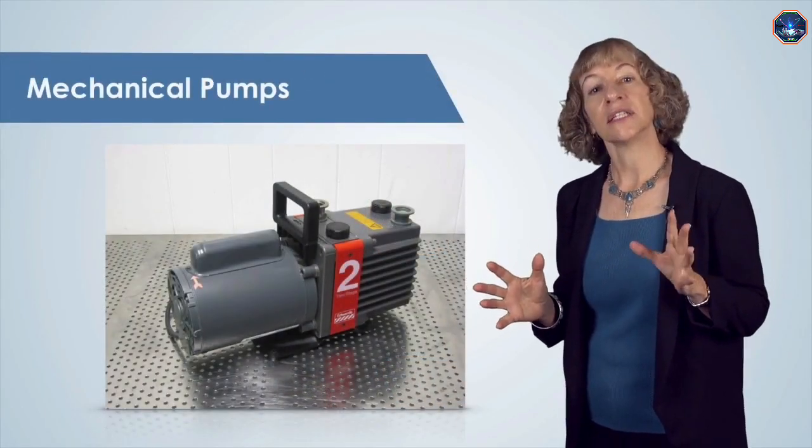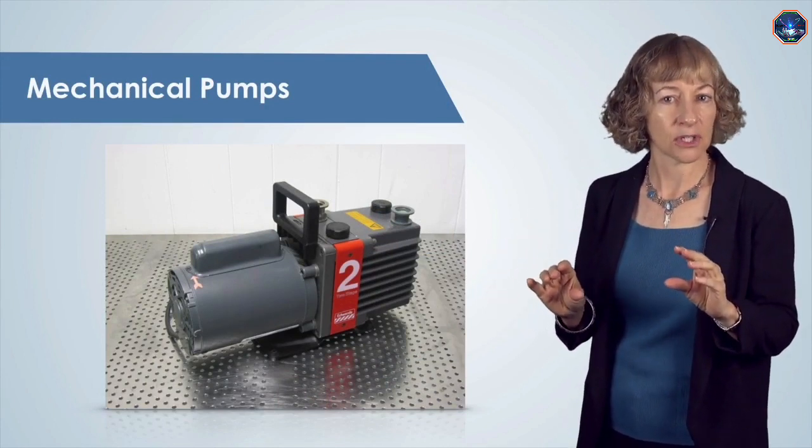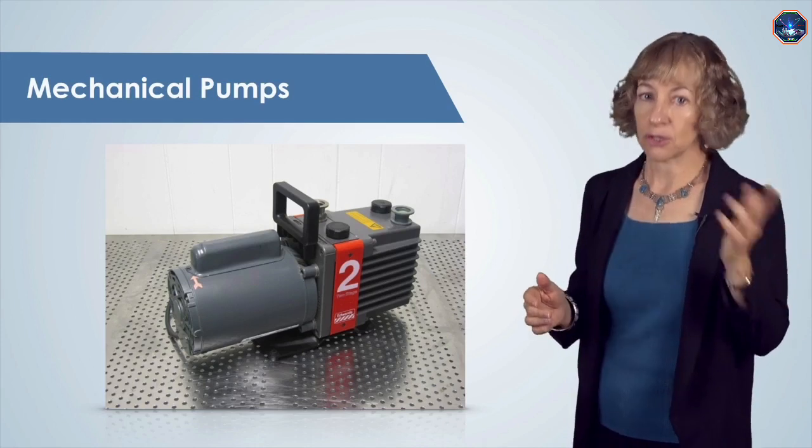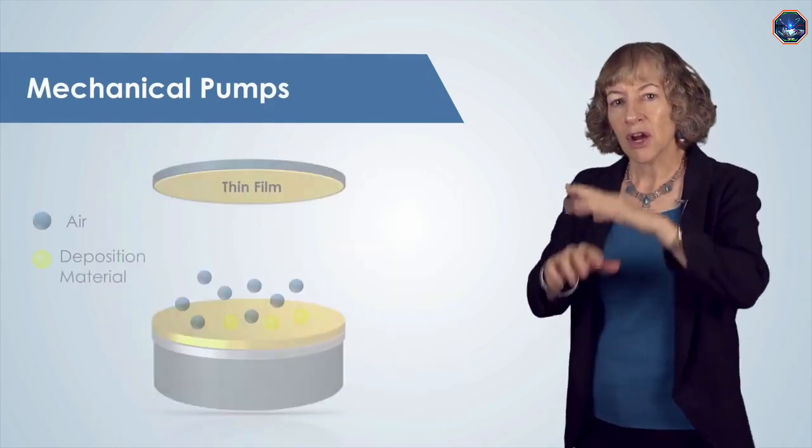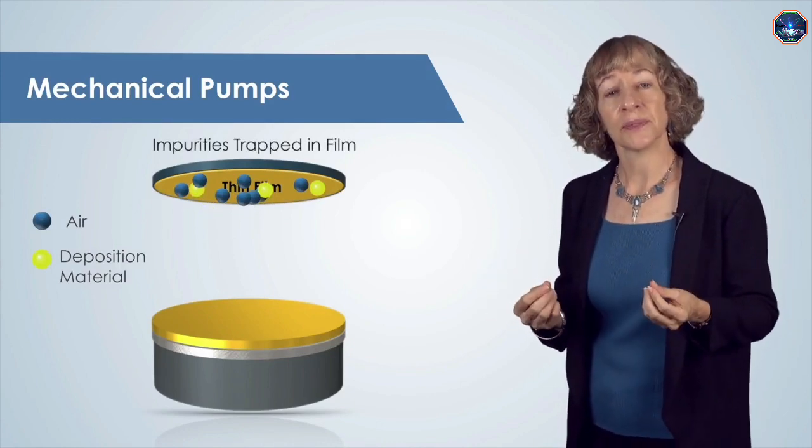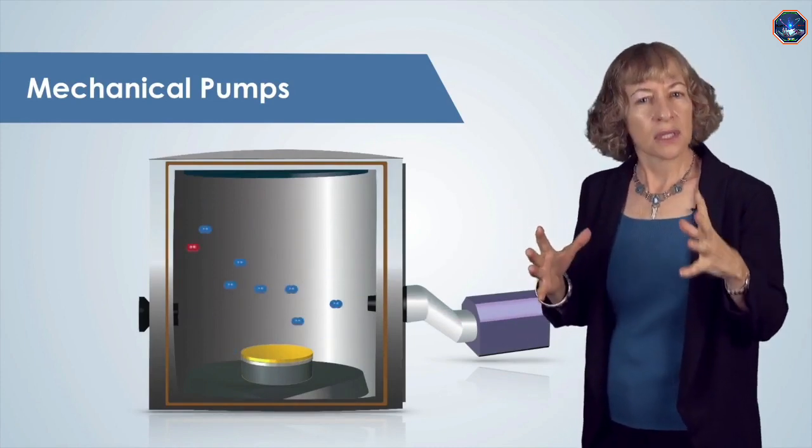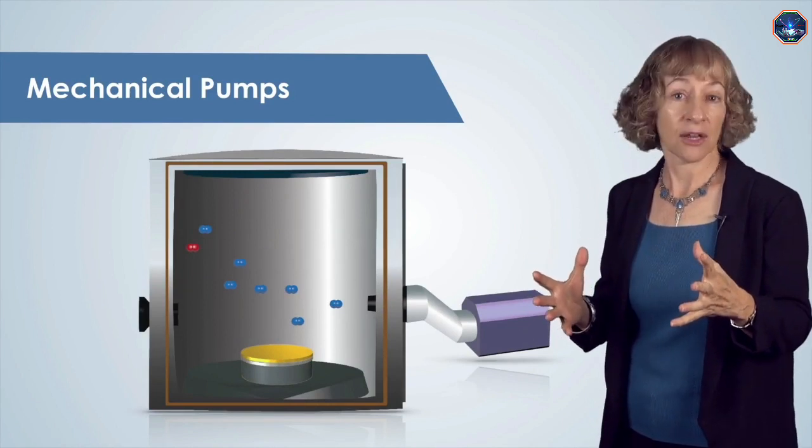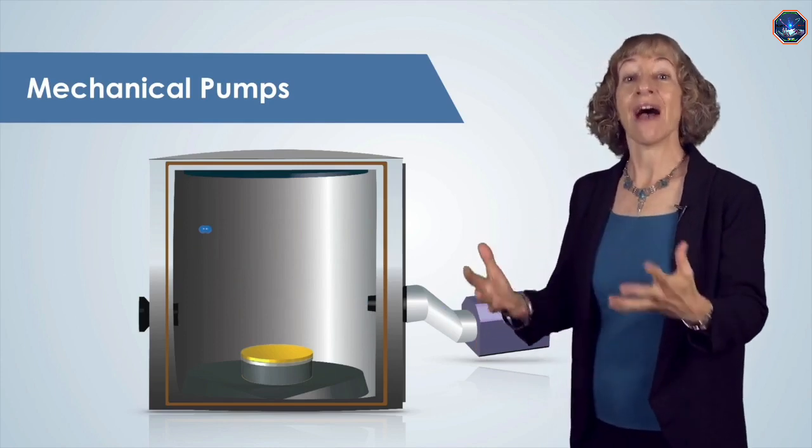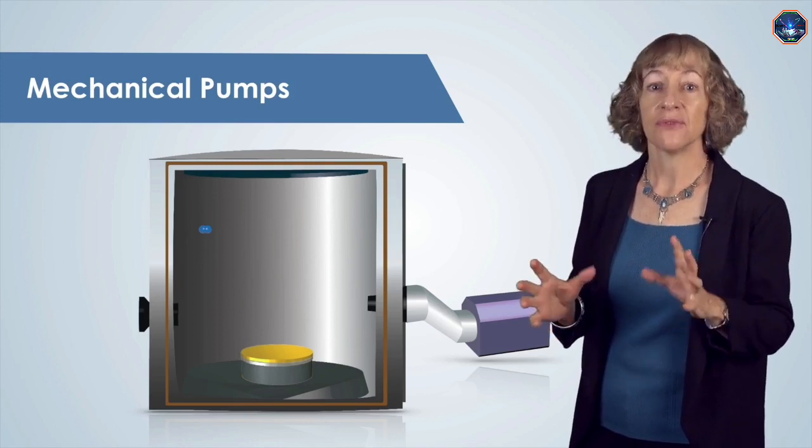Mechanical pumps alone cannot typically reach pressures low enough for thin film high-quality deposition, so we need to use another pump—a high vacuum pump—in addition to the mechanical pump. Remember that air molecules in the vacuum chamber will introduce impurities in the deposited film. We can use mechanical pumps to remove some of this air, but there is a limit to how many air molecules a mechanical pump can remove, so we need to continue to pump after we use a mechanical pump to achieve much lower pressures.